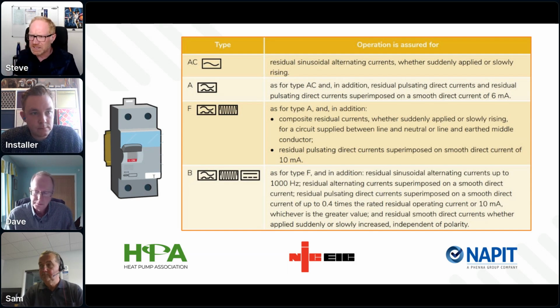But table 1 starts with, like Sam mentioned, the type A RCD, and it gives you those clear tolerances for pulsating DC currents. I'm not going to go over those again because Sam's covered them. But what we've got to realise is that some heat pumps will work perfectly okay with a type A, and some manufacturer's instructions will say that, because they end up with equipment that hasn't got those complex inverters or drives or electronics in that particular system.